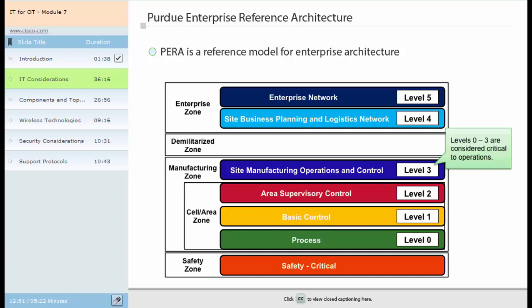A cell area zone comprises Level 2, Area Supervisory Control, representing systems and functions associated with the runtime supervision and operations of a cell area zone. Depending on size and complexity, these functions may also carry over to Level 3. Level 1, Basic Control, consists of interfaces to the Level 0 devices, input-output, linking devices, bridges, and controllers. The controllers may be standalone in single controller applications, or multiple controllers on a peer-to-peer network. Level 0, Process, is comprised of a wide variety of sensors and devices to monitor and control both discrete and analog variables, performing the basic functions of monitoring and controlling the cell area zone. Devices can be traditional hard-wired devices, or more sophisticated network devices which take advantage of advanced configuration and status information.